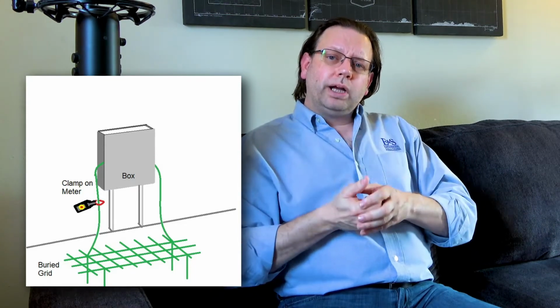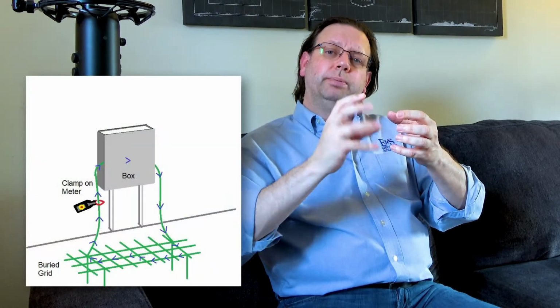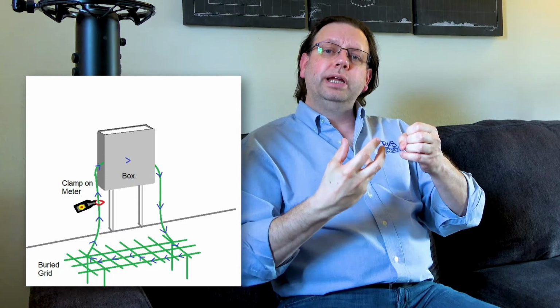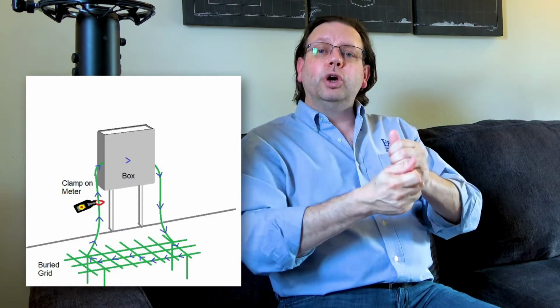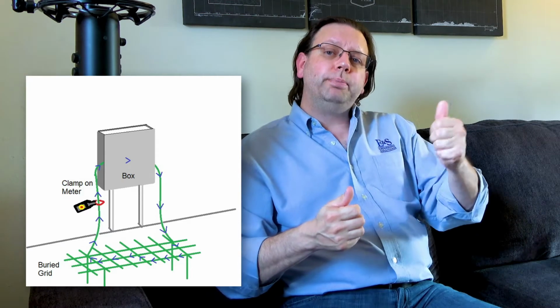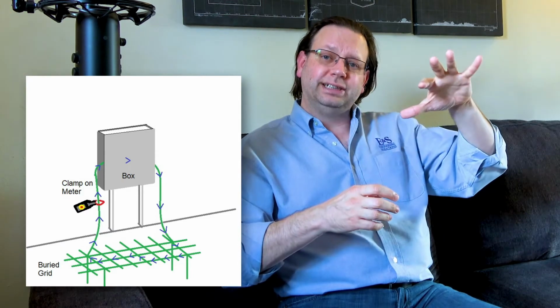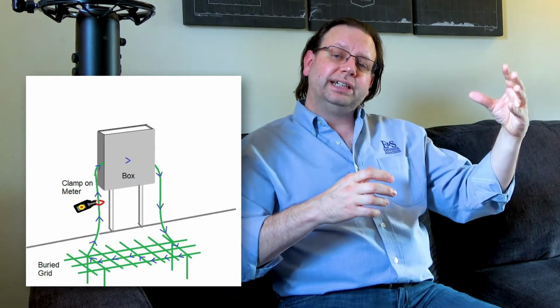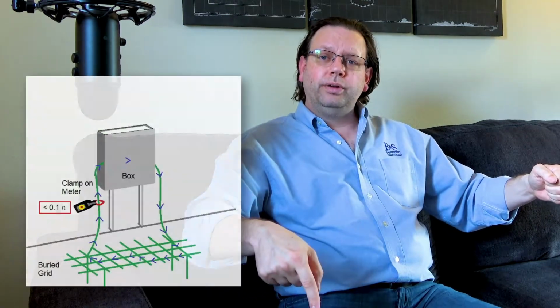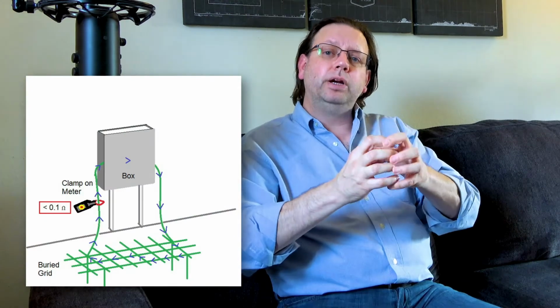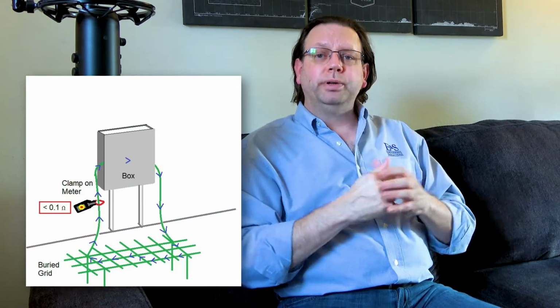So if we walk up to one of those ground wires and clamp onto it, the active coil is going to start oscillating back and forth. It's going to induce a current into that ground wire, and it's going to go both directions. In one case, it's going to go up into the piece of equipment through the chassis that it's bonded to, across that chassis, down to the second ground wire it's tied to. And it's going to go down to the below grade grid. It's going to find a path through that ground grid back to the meter and go up that ground wire back to the meter and show us the overall drop in resistance.